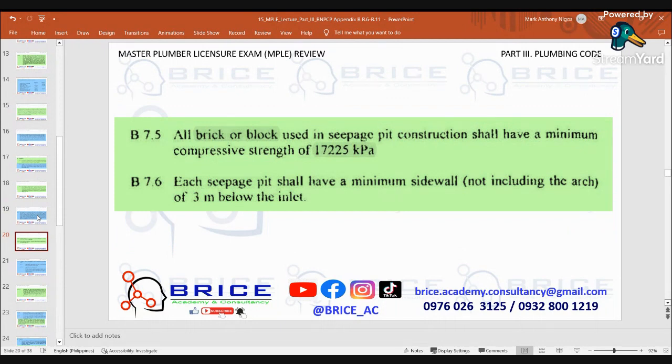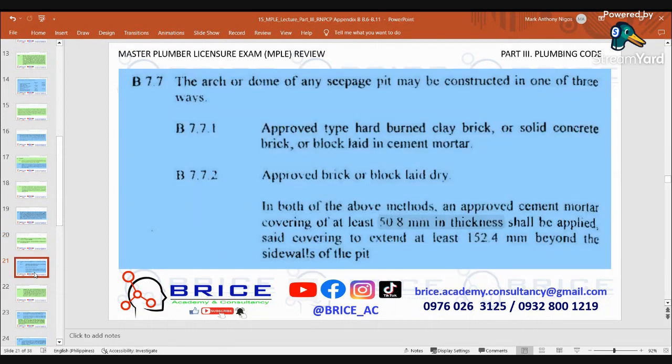All brick or block used in seepage pit construction shall have a minimum compressive strength of 17,225 kilopascal. Each seepage pit shall have the minimum sidewall, not including the arc, of 3 meter below the inlet. Yan.